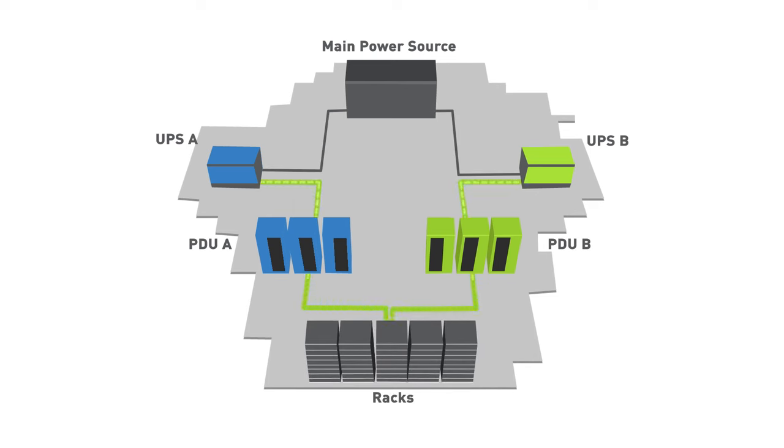The rack PDU in each rack plugs into the outlets. Most servers now have two power supplies, and it's important to plug each power supply into a different rack PDU. This way, if a UPS should fail, then the connected floor PDU and RPP will fail, and one rack PDU will fail. If properly configured, the other rack PDU along with the other power chain will remain operational and your servers won't go down.